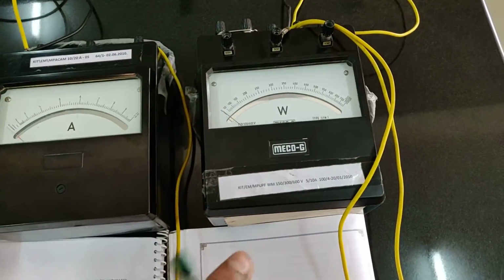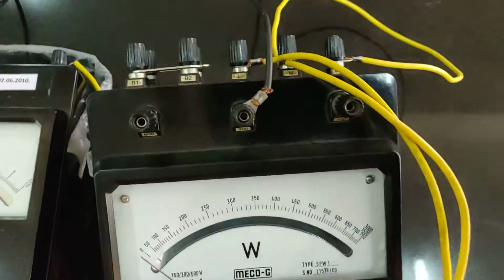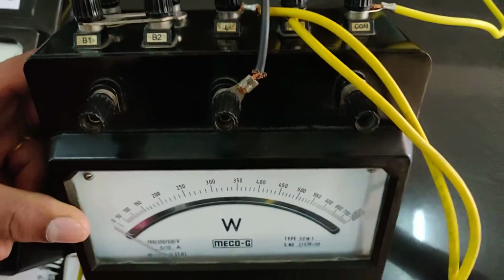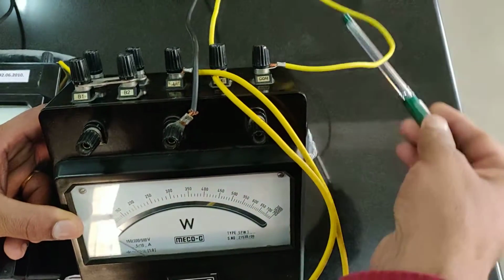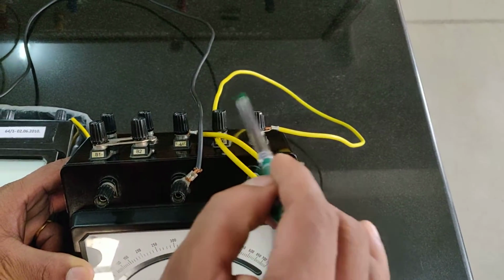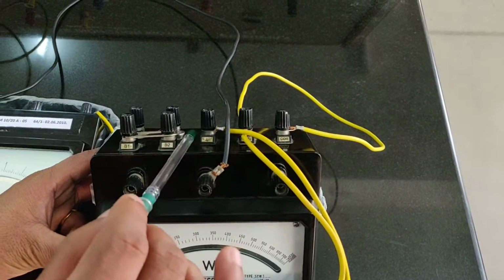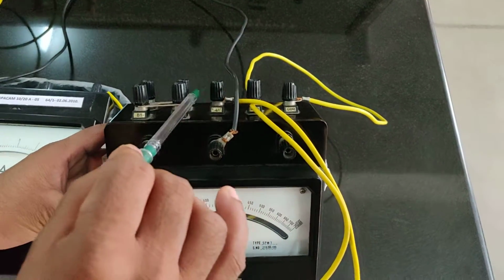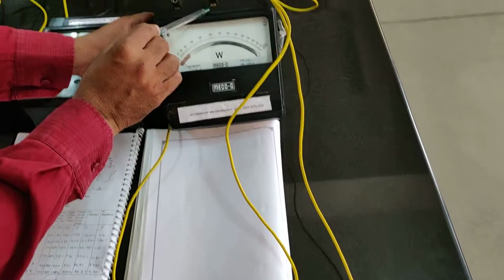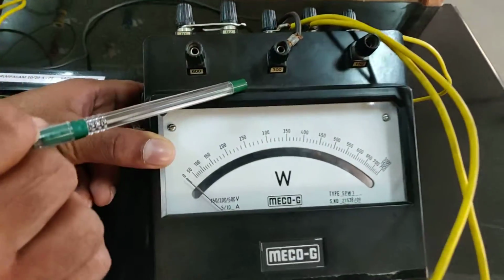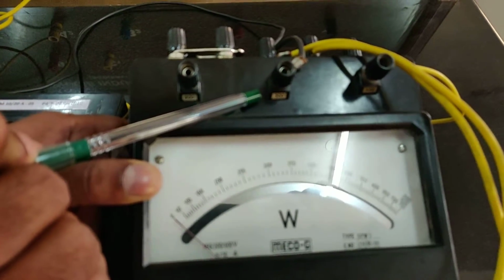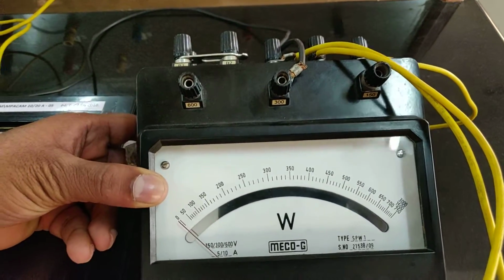The wattmeter - when I say wattmeter, I am using a UPF wattmeter here, because the load connected is resistive. Normally we will see M and C, where M is the main, C is the common terminal, and L is the load terminal. A yellow color wire is going to the load, and here the V is the voltage potential. Here I have connected 300 volts, because it's single phase - I have connected the 300 volt voltage potential.